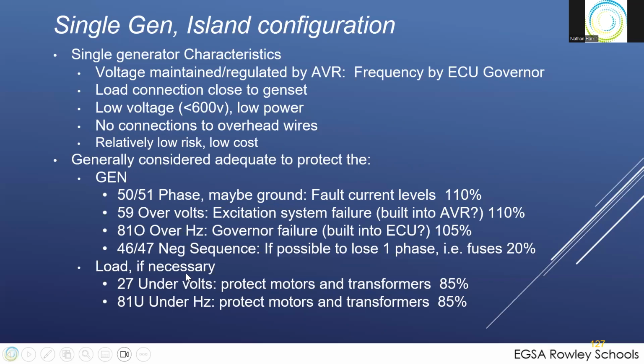Now, the generator doesn't care if it runs under speed or under voltage, but your load might. So if you have transformers and motors, you may want to protect them. In that case, you'd want to set under voltage, under frequency. This is not to protect the generator. This is to protect the load, right? And so if you're just load banking, don't worry about it. Load resistors don't care. But if you're feeding the load transformers and motors, then yeah, you probably want to set under voltage and under frequency.